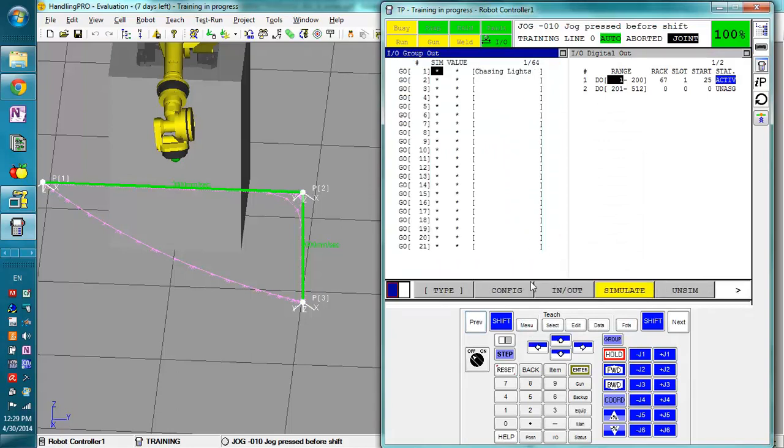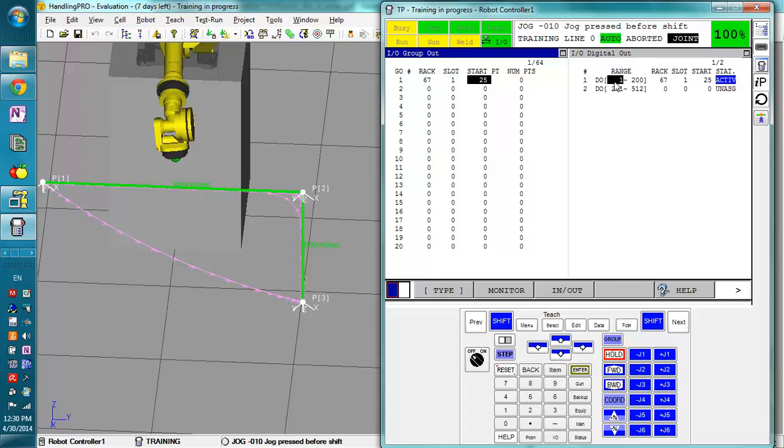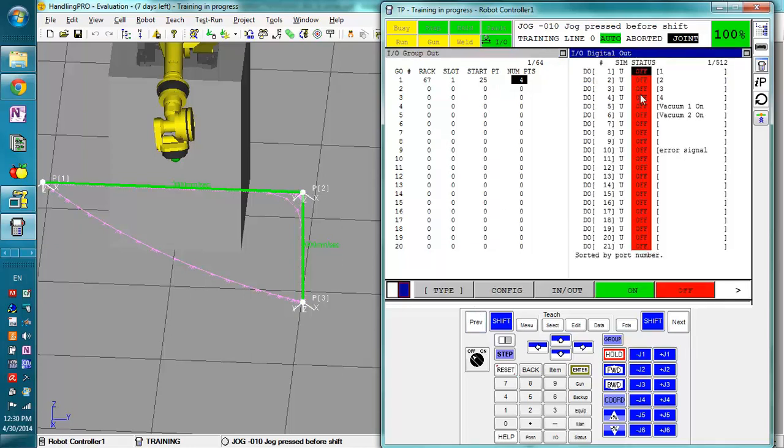Now I'm going to go to configure. And for this group output, we want Rack67, Slot1, StartPoint at 25, because DigitalOutput1 starts at 25. So that's DigitalOutput2 is 26, then 3 is 27, 4 is 28. So we just need to tell it how many points there are. There are four points. So what this will do, it starts here, and the four digital outputs right there are included in this group output.